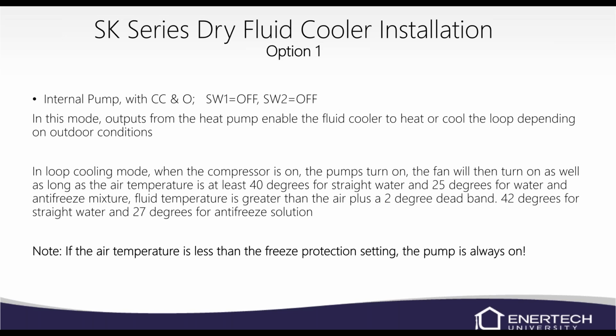If the air temperature is less than the freeze protection setting, the pump will run all the time. And that's to keep that fluid moving so we don't have to worry about it freezing up, obviously.